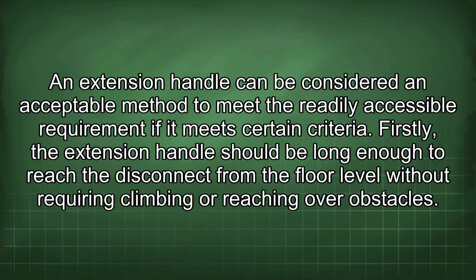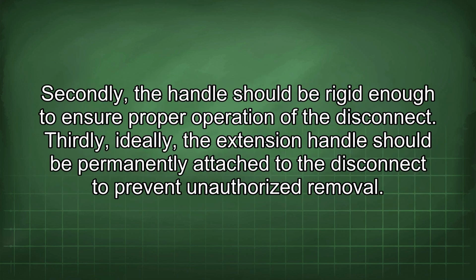Firstly, the extension handle should be long enough to reach the disconnect from the floor level without requiring climbing or reaching over obstacles. Secondly, the handle should be rigid enough to ensure proper operation of the disconnect. Thirdly, ideally, the extension handle should be permanently attached to the disconnect to prevent unauthorized removal.